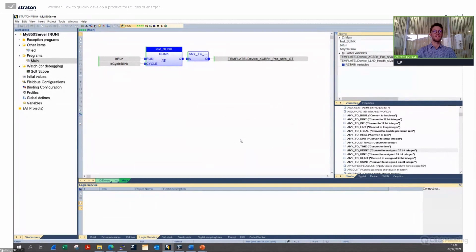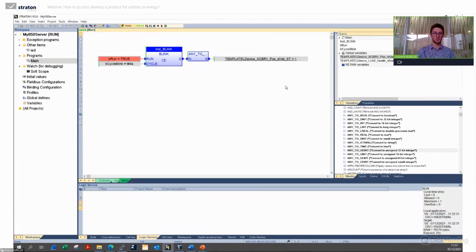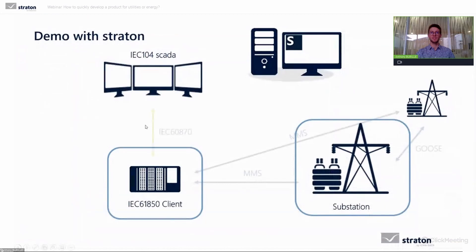I go online — it asks if I want to download the application. I say yes. Very quickly it downloads the compiled files to the target, and now clicking Run we see the circuit breaker position blink from zero to one. My 61850 server is running — I've transformed a Raspberry Pi into a substation with a circuit breaker having its position blinking from zero to one.